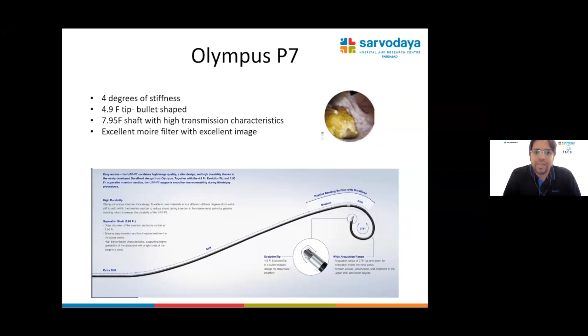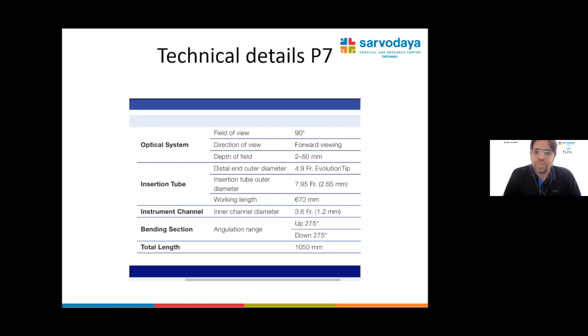So if we talk about technical details, as I mentioned, the diameter of the scope is 7.95 French, the tip being thinner, and it's a forward viewing scope with field of view of 90 degrees, the length of 670 millimeters, and an inner channel diameter of 3.6 French. This is standard in every scope. Almost every scope, the diameter of the instrument channel is 3.6 French. So this is the image quality we get with the P7. As you can see, it's excellent image quality. We can clearly see the stone, we can clearly see the fiber, and we can even see the dust that is floating around. And there's no Moiré effect there.